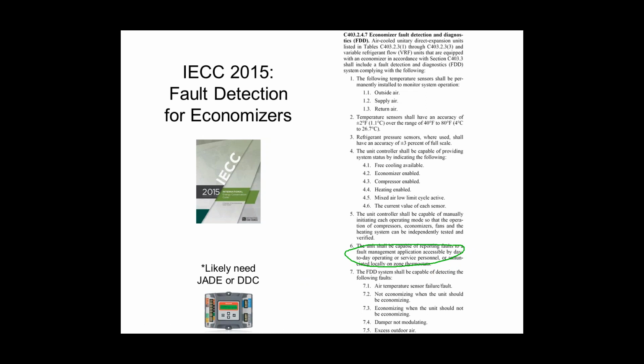So the Jade is what you've got to use anyway down the road, unless your manufacturer has their own controller, which is fine. But if you're using Honeywell stuff, then you've got to have a Jade controller on all projects, on all rooftop units, on all air handlers with economizers. And then you need to have a thermostat that has an input on it where the Jade can send an output. The Jade will track these same alarms we're talking about here, all of them, and it'll close a contact closure to send a signal down 2 wires to your thermostat, and your thermostat has to have an input that picks up that signal and then annunciates it on the front of the stat. There are stats from Honeywell that do that, obviously. There are stats from Venstar that do that, and I'm sure there are probably other ones out there as well. But you definitely have to do that.